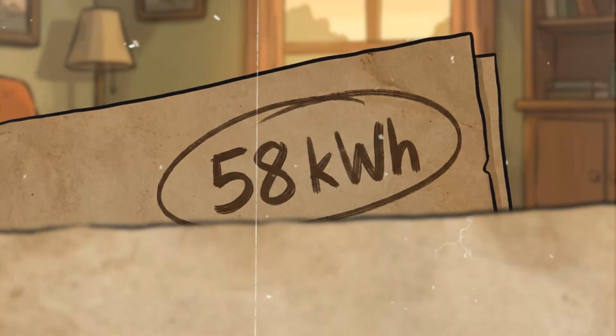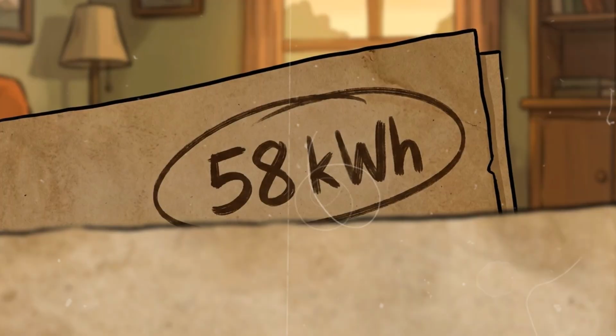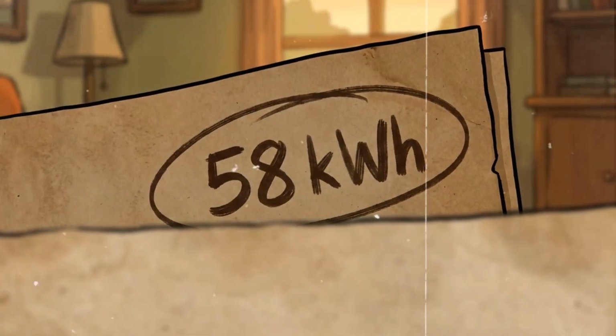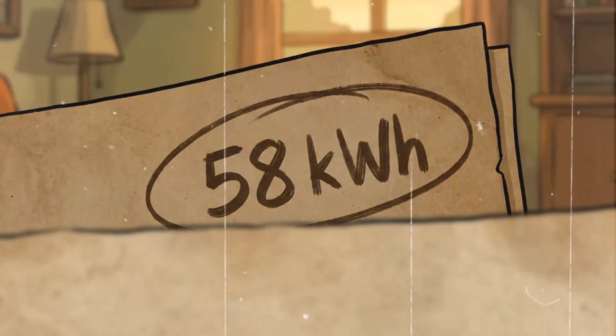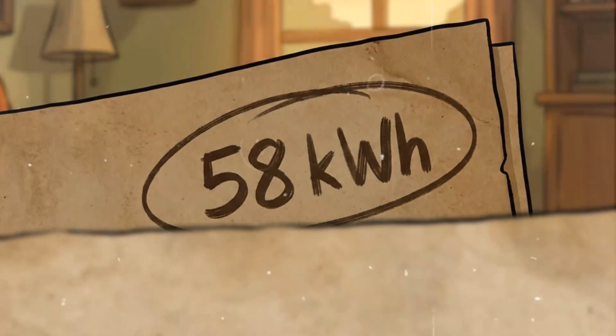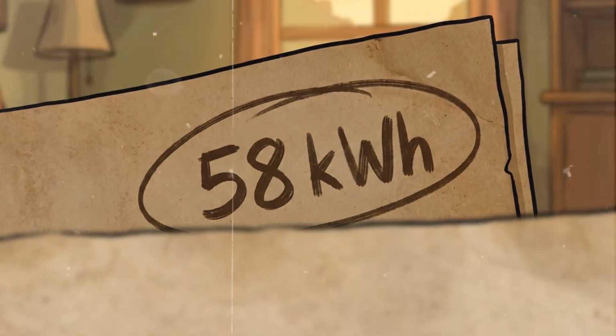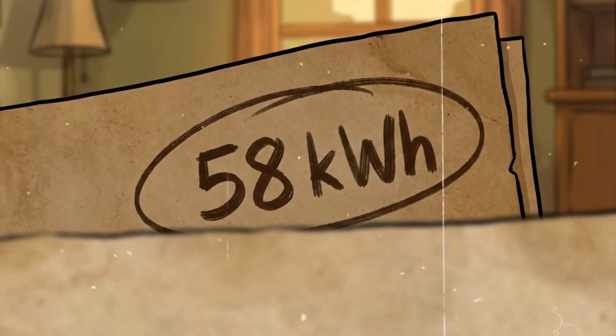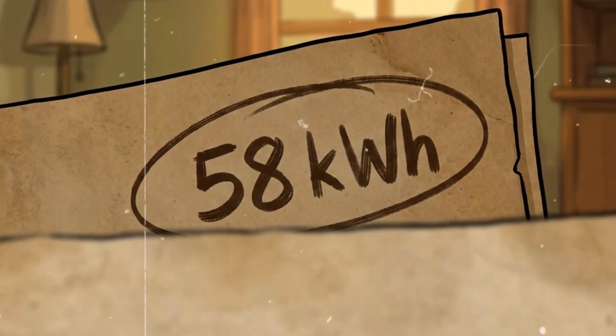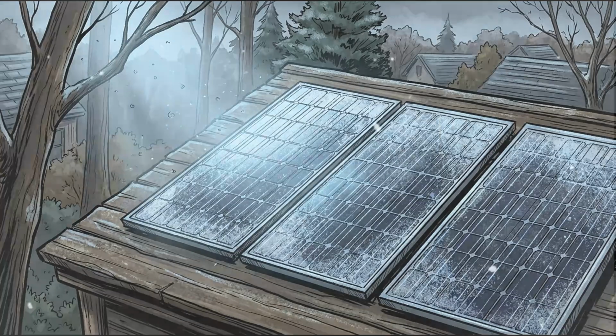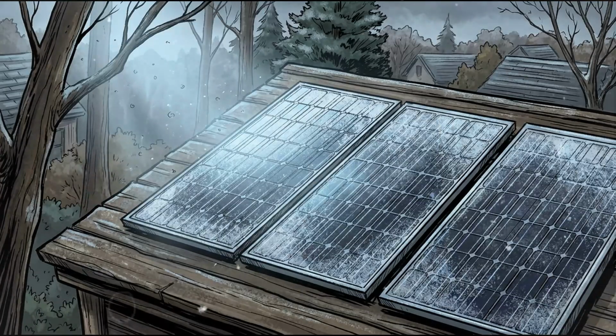Now match that requirement against your sources. 800 watts average draw for 72 hours is 58 kilowatt-hours total. Your 1 kilowatt-hour power station covers less than 2% of that requirement. Your gas generator covers it, but burns approximately 35 gallons of fuel.